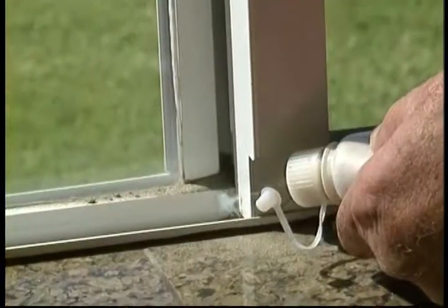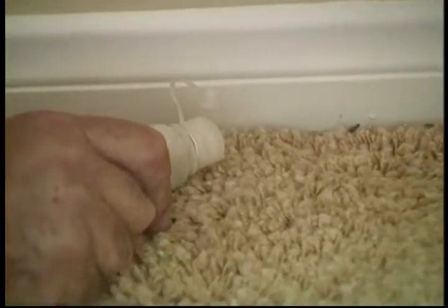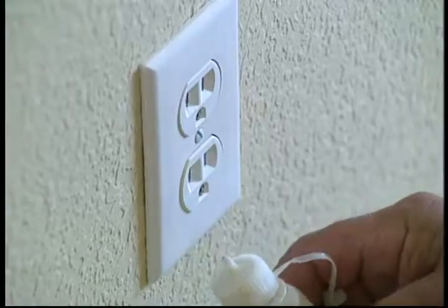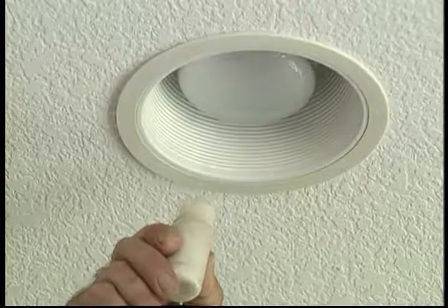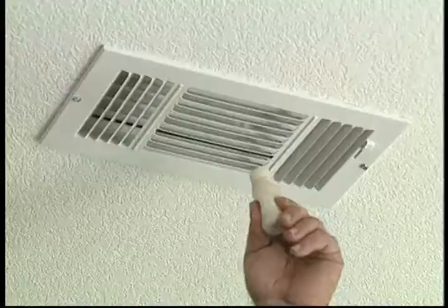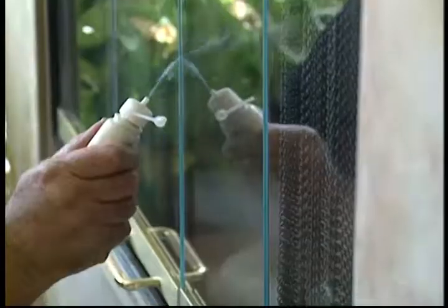So in summary, basically what this device does, it just pressurizes the house, and you measure the airflow through it, and then you can also go around with a smoke pencil and find out where the leaks are at? Yeah. In fact, we'll be doing that, Steve. The leakage sites are typically around the windows, around the doors, bottom plates, receptacles. A big one is ceiling lights. Ceiling lights leak a great deal. Dampers, duct systems. A huge one usually is fireplaces.